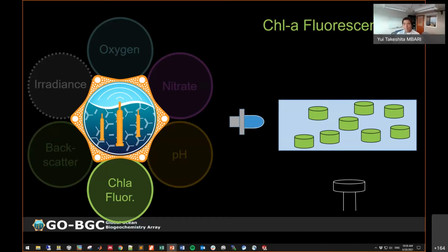In practice, you modulate the excitation light source to filter out some of the ambient noise in the light. Currently, these sensors use an excitation wavelength of 470 nanometers and measure the emission at 695 nanometers. The sensing technology is very robust for fluorometers because it has a very long history, and it's a very mature sensor. The challenge is how you convert fluorescence, which is what the sensor measures, to the properties you care about, which are chlorophyll concentration and ultimately biomass. I will walk through that towards the end of the talk.